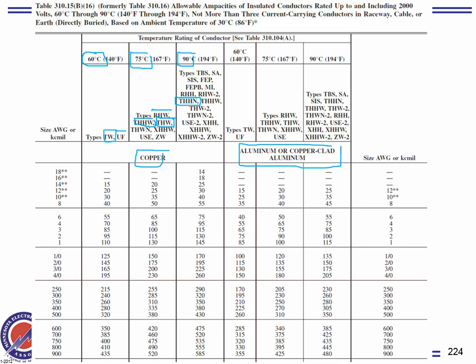So here's how they catch you. I want to bring to your attention this weird conductor right here. Can you guys see? How is it looking on your side? This is THHW. Look at this conductor here, right? The same conductors are in two columns. When do you use it? This means, guys, if it's used in a wet location, it's 75. If it's used in a dry location, it's 90. This is one of the most important things that we catch you on.